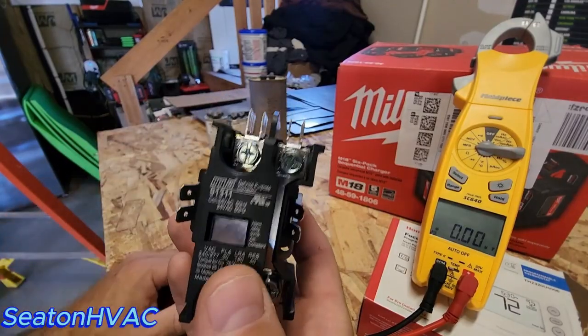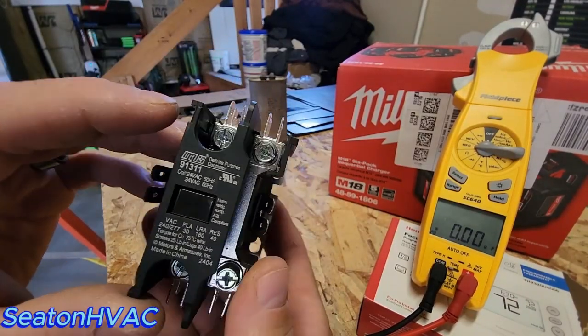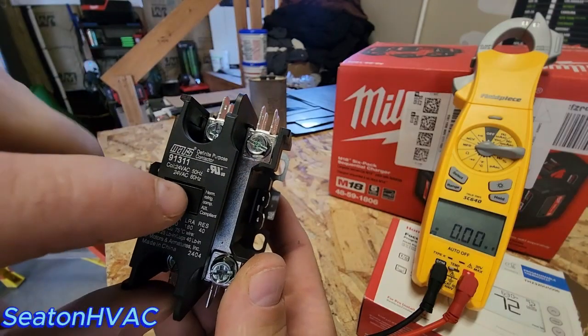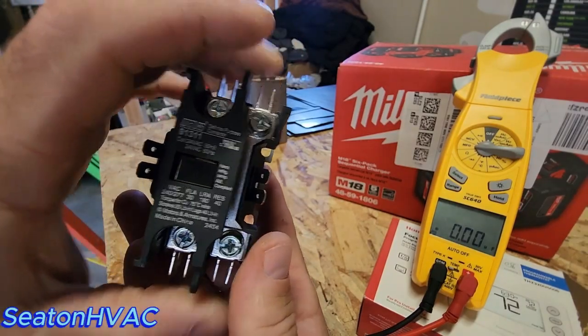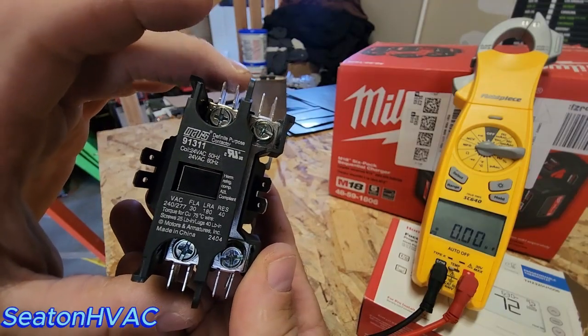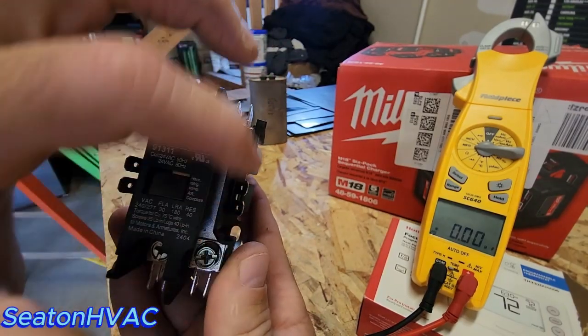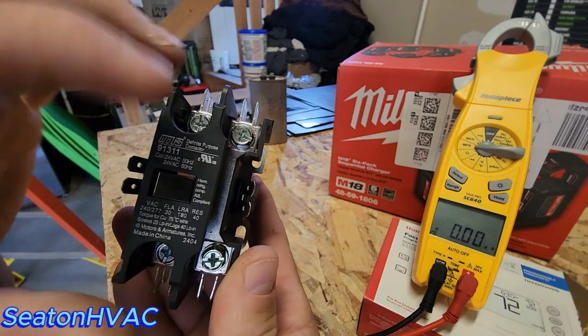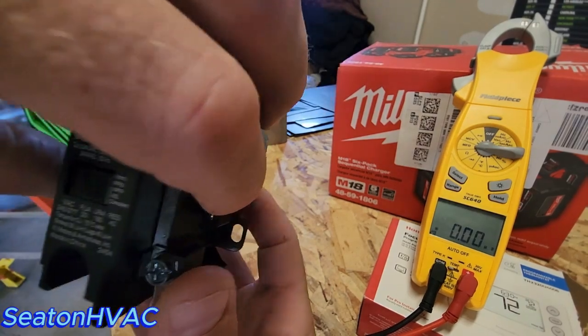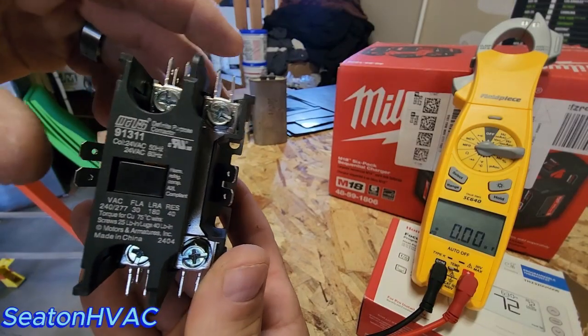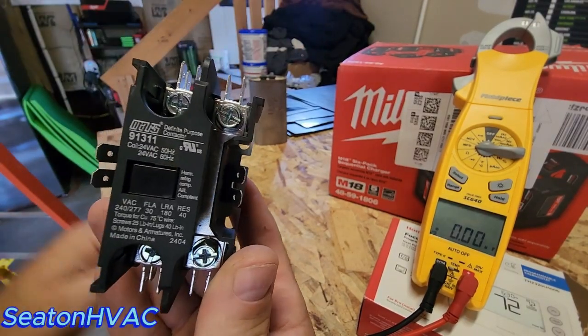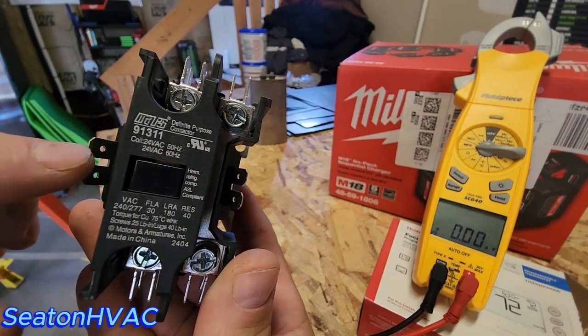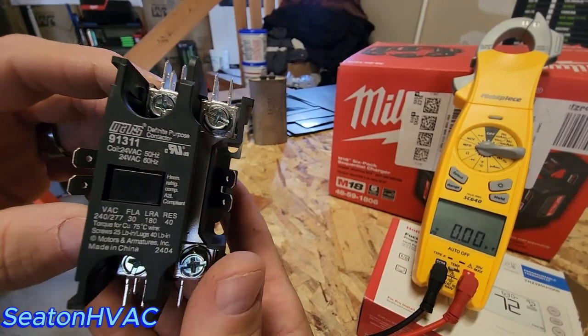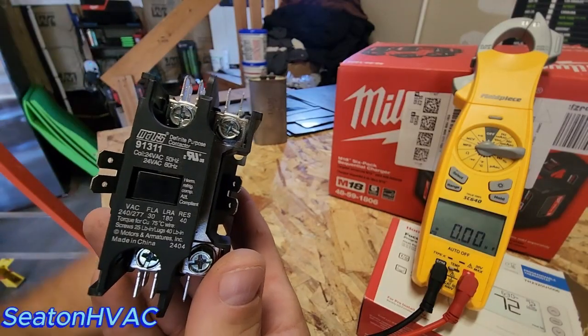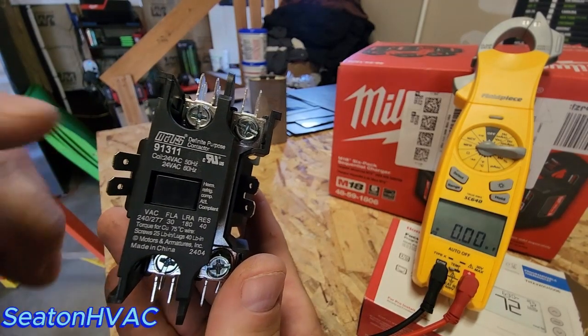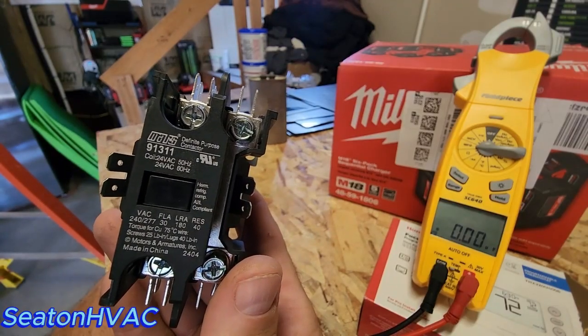So how do we test? This is what's called a 1.5 pole, and why it's 1.5 is because you never lose power based on this switch through this side, but you will on this side. So it's basically just interrupting 120 volts here, but it's not interrupting this. This stays hot all the time. So when this energizes 24 volts, you have a hot side and a common side, and they're interchangeable. You're always gonna have 2 wires there. Usually they're yellow and blue, I think, depending on what type of equipment. Some are yellow and brown, based on what they use for common. But typically it's yellow and blue or brown.